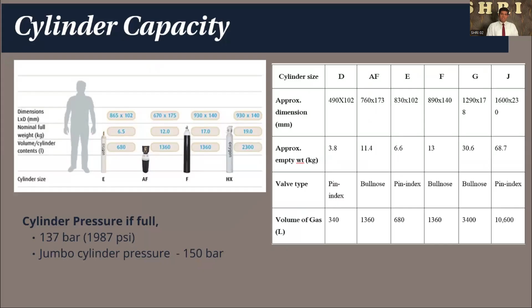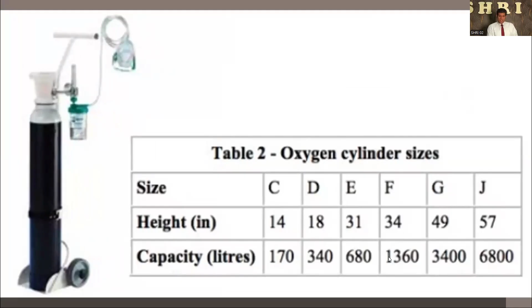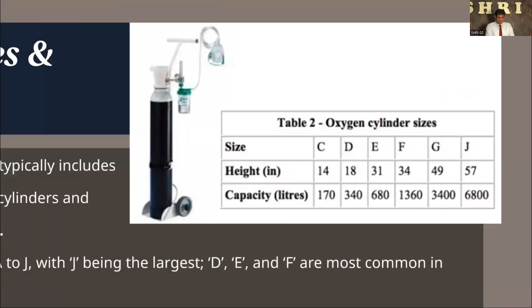When we go to gas cylinder sizes, the gas cylinder at our waist level we call the F size cylinder. The F size cylinder has a height of 34 inches and a capacity of 1,360 liters. That is the F cylinder. And we use the smaller cylinders, the D cylinders, for transportation, because we have to move the patient from the ward to the ambulance. We use D cylinders, smaller in size and easy to carry. But in the ambulance we use F cylinders with higher capacity and increased weight. So we use F cylinders inside the ambulance, two internal cylinders minimally, and one external cylinder in the ambulance, that is D size.